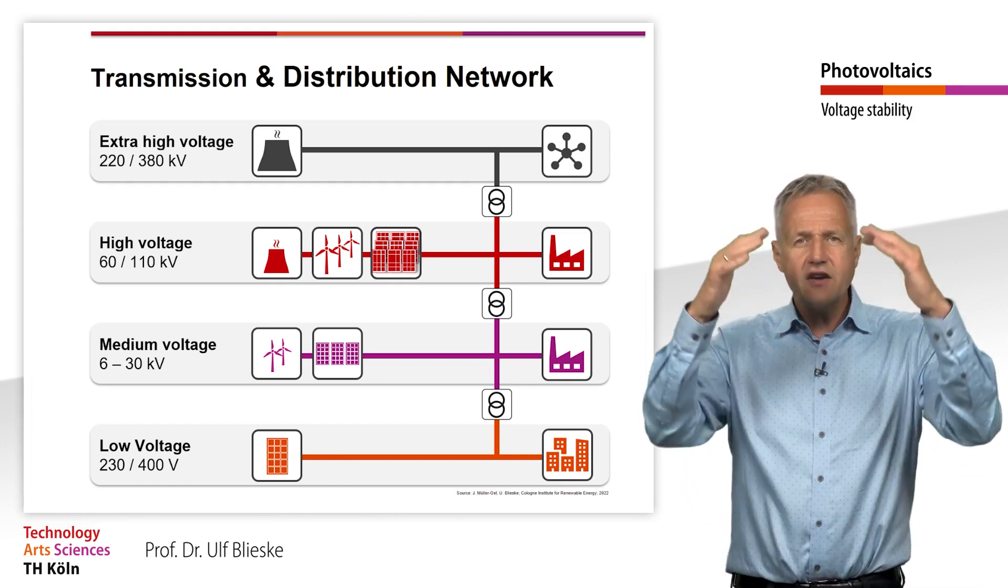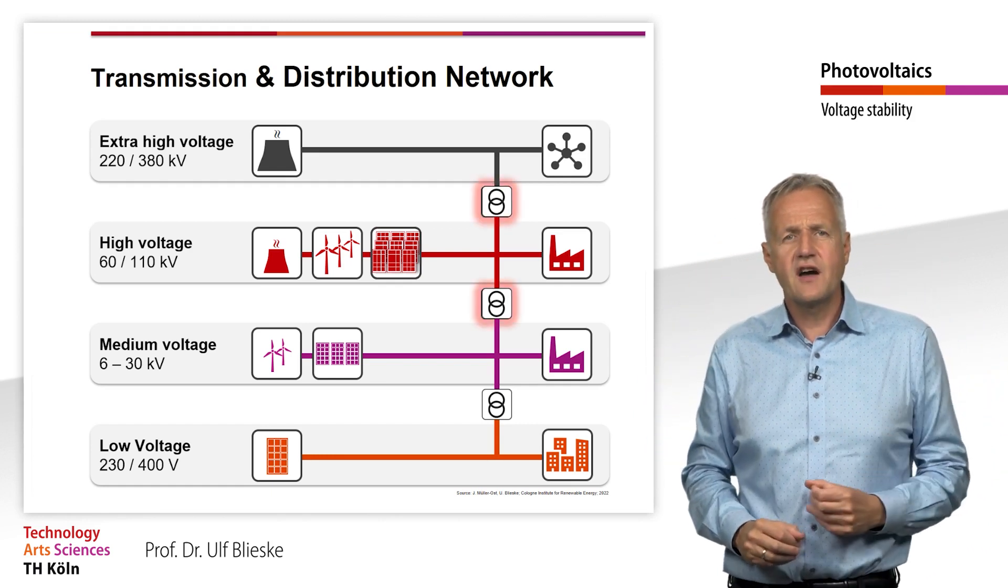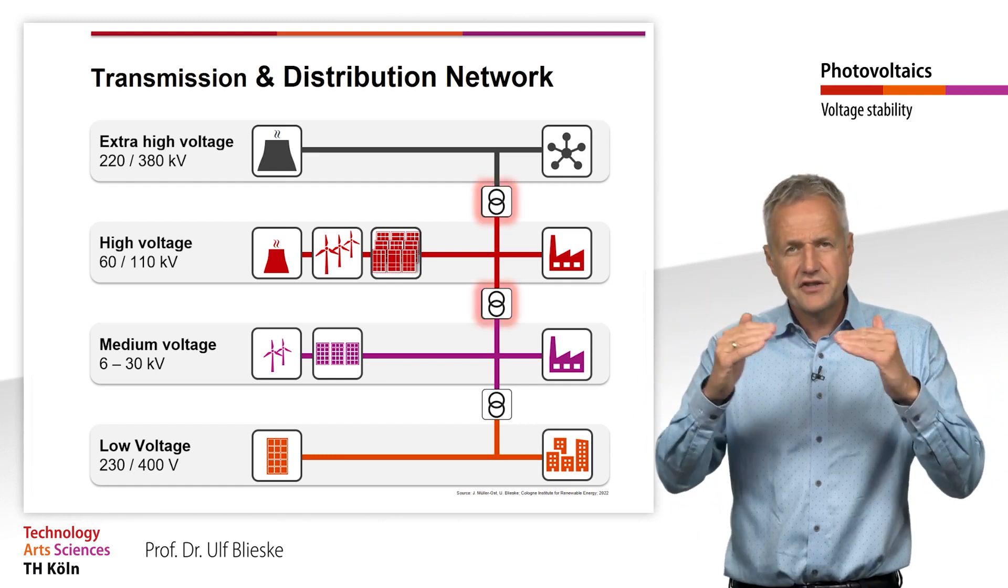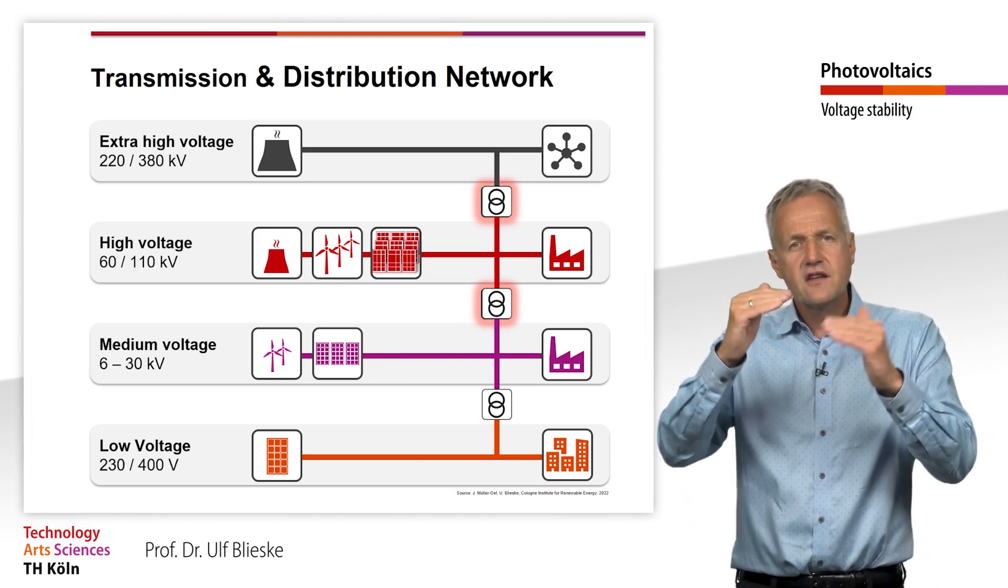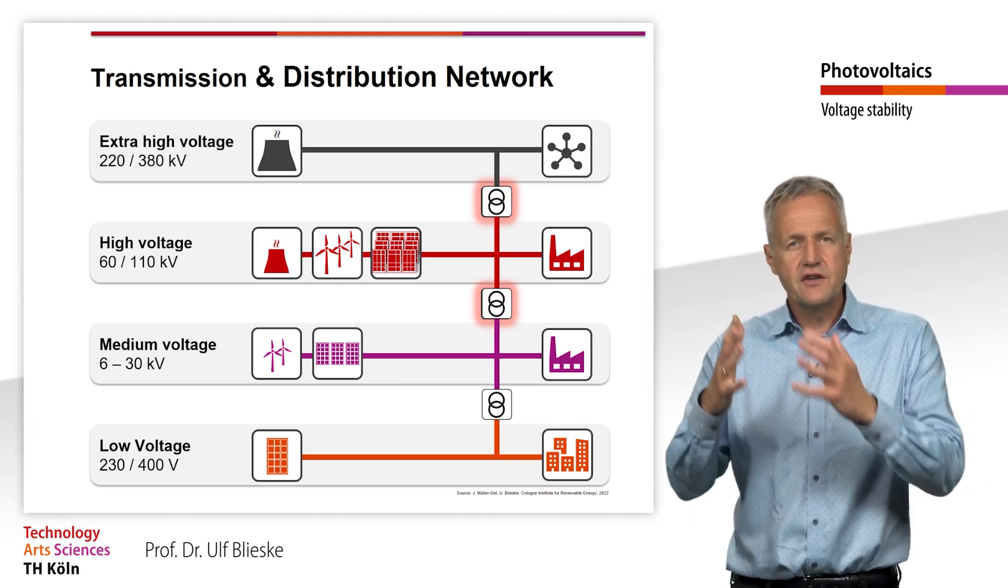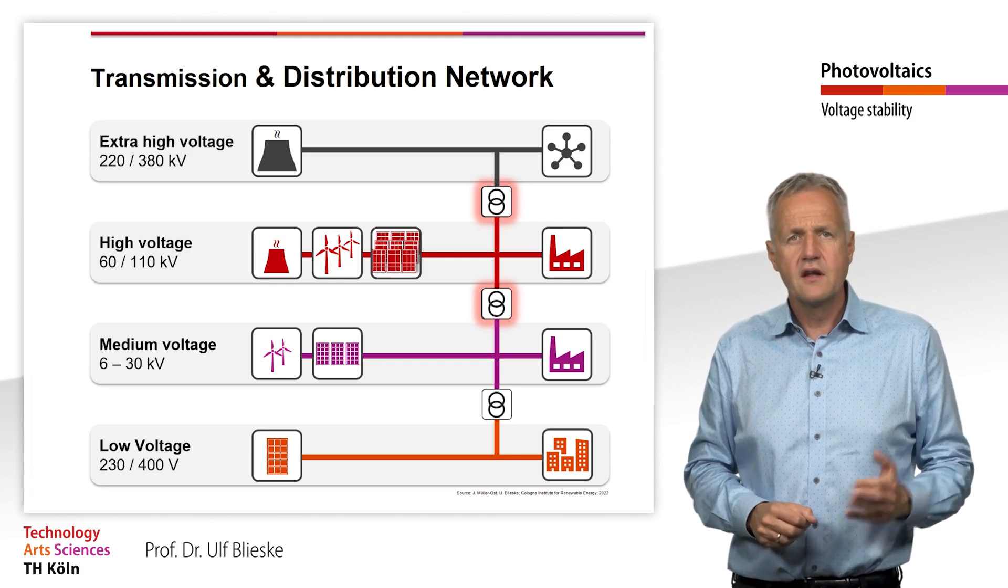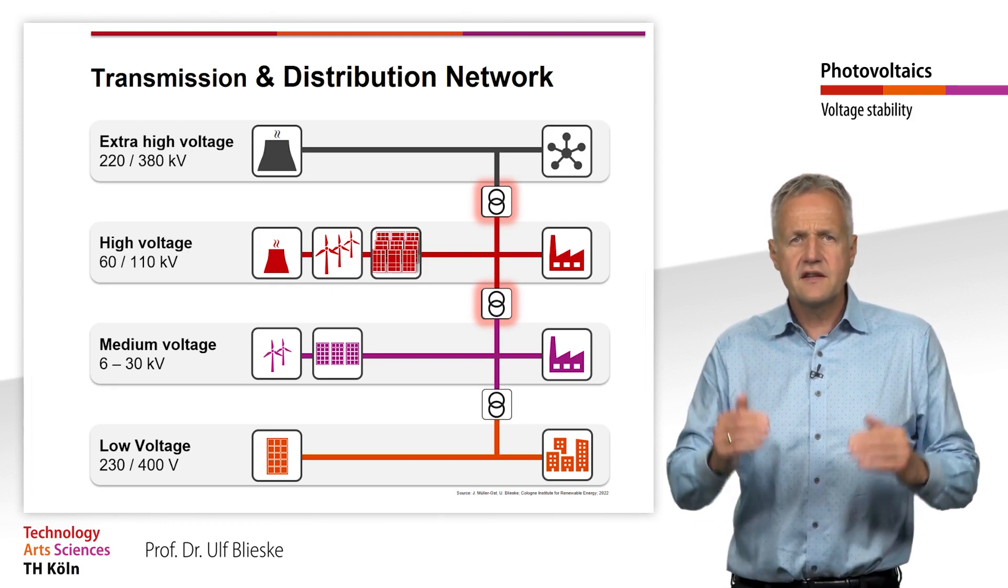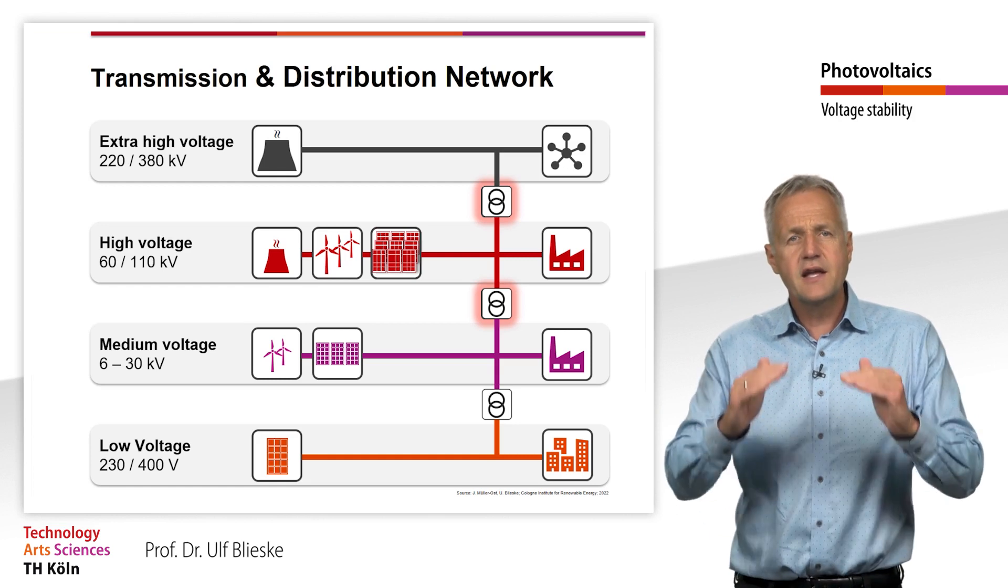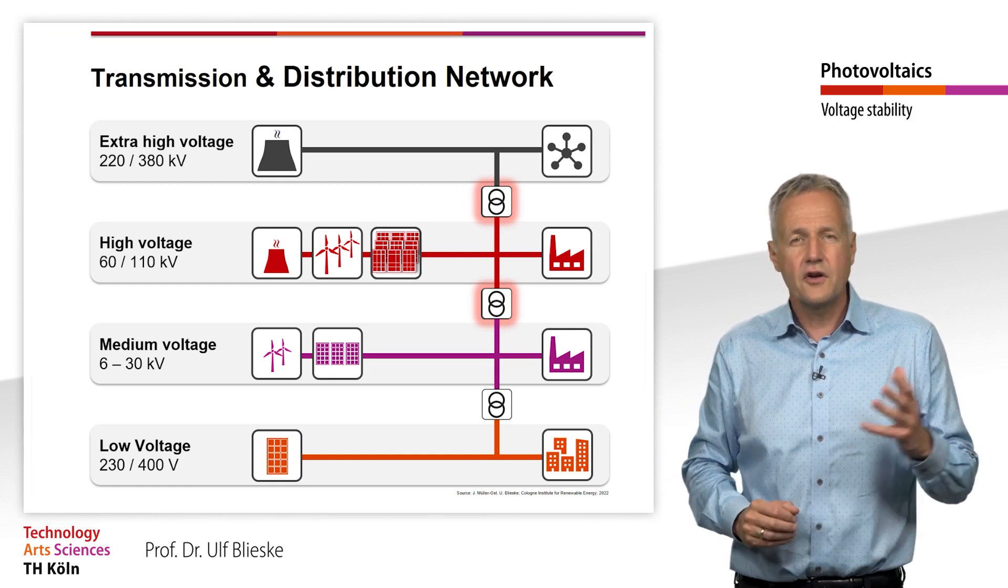From extra high voltage to medium voltage, the substations are each equipped with regulators that can adjust the transformation ratio between two voltage levels. This means, for example, that the voltage on the medium voltage side can be kept approximately constant even though the voltage on the high voltage side fluctuates due to wind feed-in.